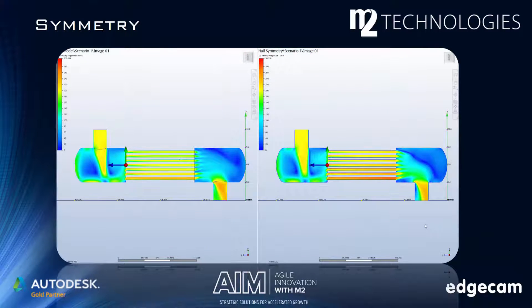That's all. Let's run them and see the difference. Here you see a cross section showing velocity through the domains of both models. They look similar. As for the hard numbers, my pressure drops for both models are within 7% of each other. That's pretty close. I may even be able to get them closer if I gave these models a little more love. Note the time savings, though. Using about half the elements in half the time, I'm able to get results that are effectively the same. I use this as much as possible for that reason.